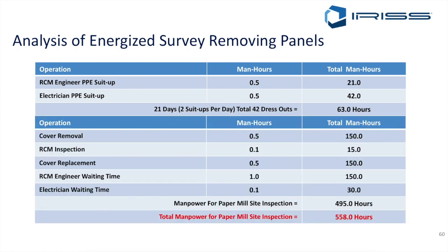The final thing we looked at was cover removal. 30 minutes to remove a cover for 2 men, so 150 covers, that's 150 man hours. RCM inspection, that's the engineer going in with the infrared and ultrasound, was 0.1 of an hour each, 15 hours. Cover replacement, another 150 hours. The RCM engineer waiting time, 150 hours - this is the guy sitting there watching electricians put on and take off panels. And the electricians' waiting time watching the guy do his survey was 30 hours. So the manpower for the inspection was 495 hours. Add the PPE suit up time, and we had an estimated 558 man hours to do this task.